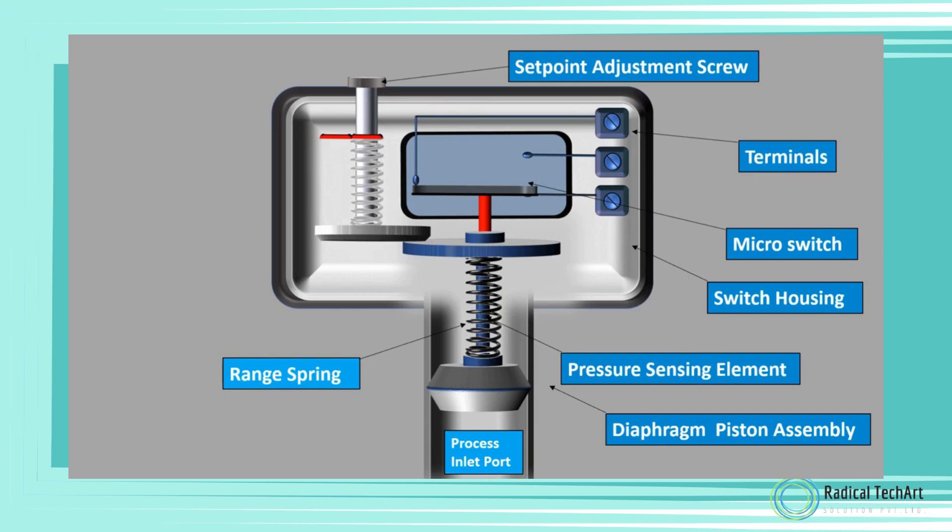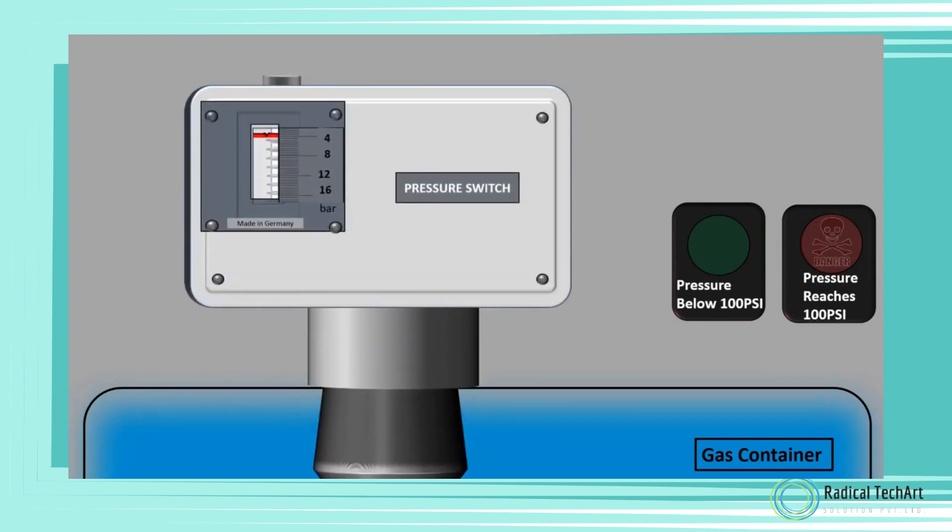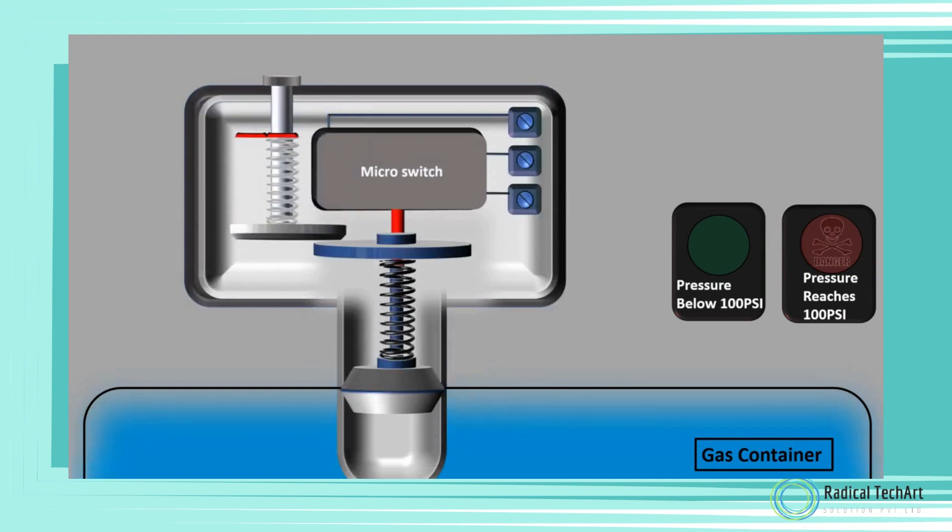Working of a mechanical pressure switch: Consider that we have a gas container and we need a green light to switch on when the pressure inside the container is below 100 PSI and a red light to switch on when the pressure reaches 100 PSI. For this, we install a pressure switch on this container and adjust the setpoint of this pressure switch at 100 PSI by turning the setpoint adjustment screw.